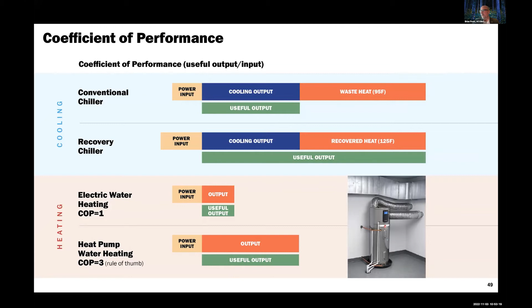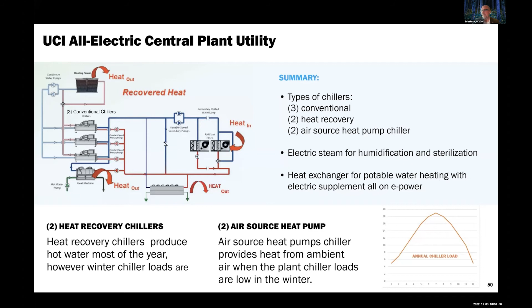So the upper left shows a conventional chiller with a cooling tower, handles heavy cooling loads. Below that are the heat recovery chillers showing hot water pumped into the building heating system. The air source heat pump chillers provide heating water in the winter when chilled water demand is low. Annual chiller load may drop in the winter to 5% of the peak load, so air source heat pump chillers are required in the winter to provide heating. The chillers are robust, reliable, and redundant, and the design build team has put a lot of effort into coming up with the design for this approach.